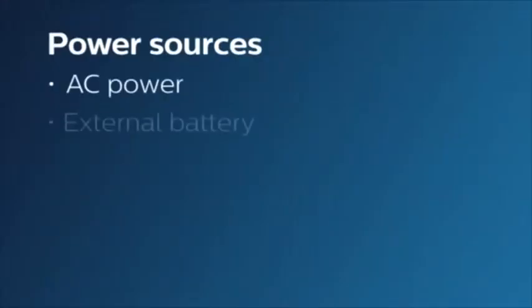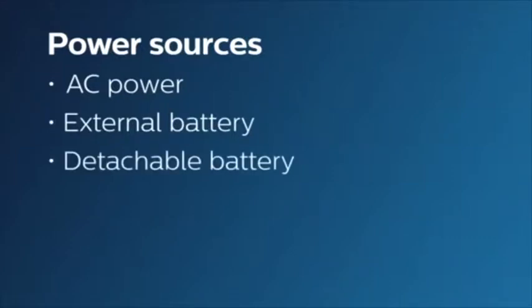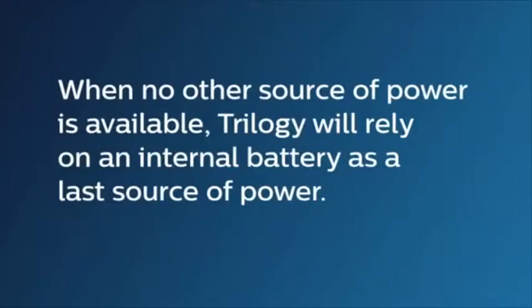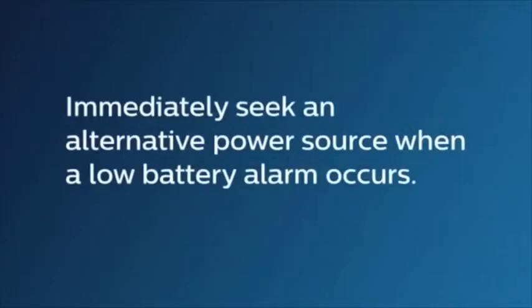Trilogy can be powered by 4 different sources: AC power, an external battery, a detachable battery pack, and an internal battery. The device will always use AC power if available. When AC is not available, it will run on its external battery if connected. If the external battery loses its charge, Trilogy will run from the detachable battery pack. When no other power source is available, Trilogy will rely on its internal battery as a last source of power. Immediately seek an alternative power source when the low battery alarm occurs, because loss of therapy is about to occur.